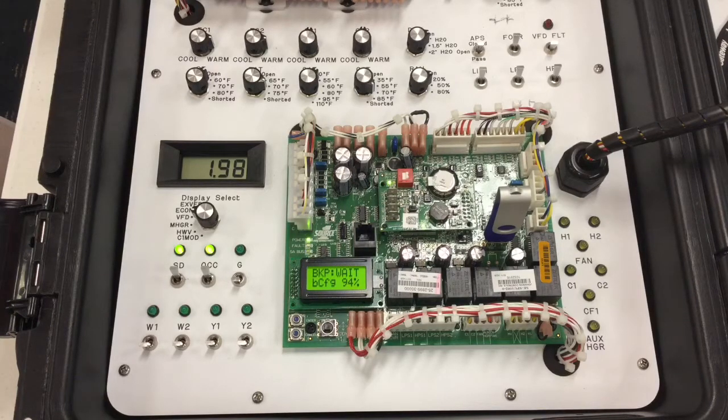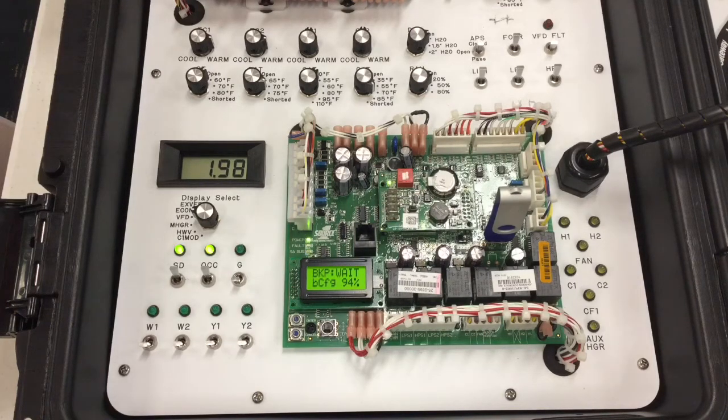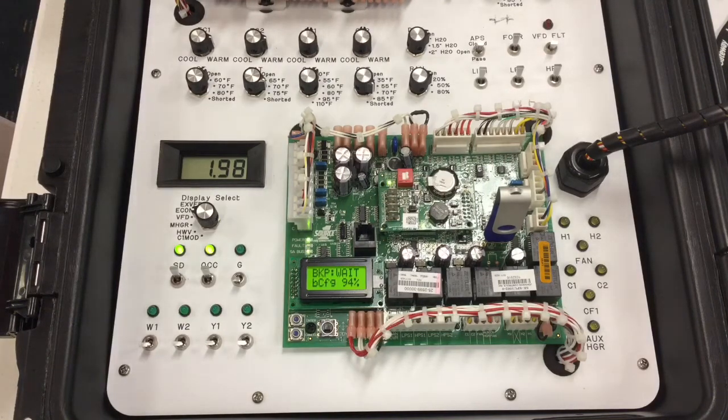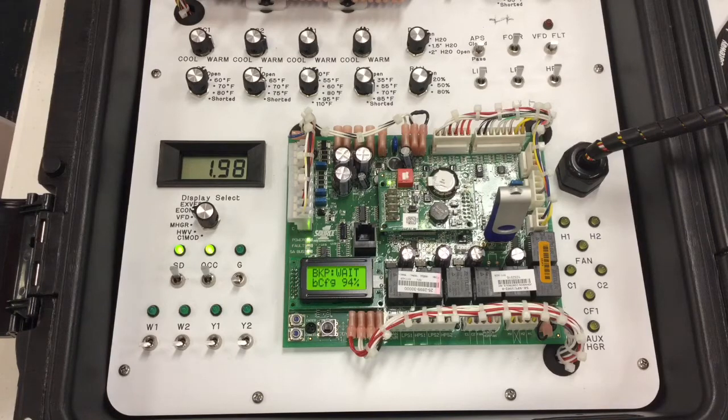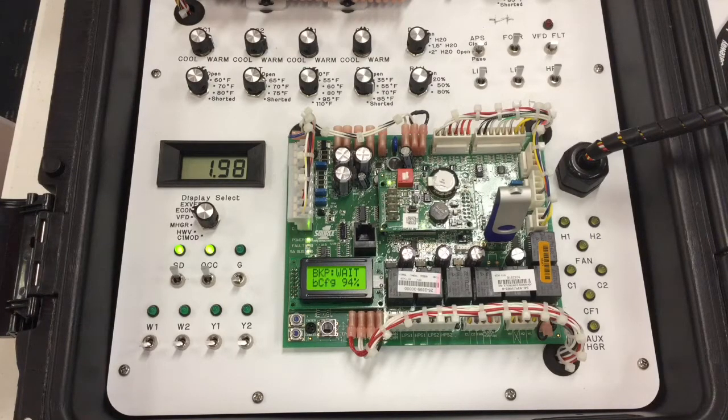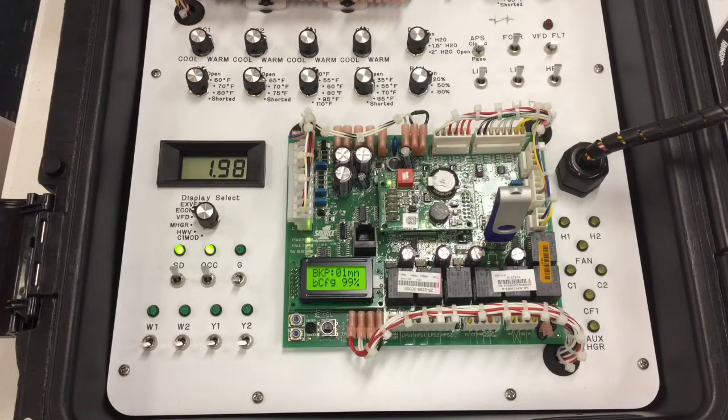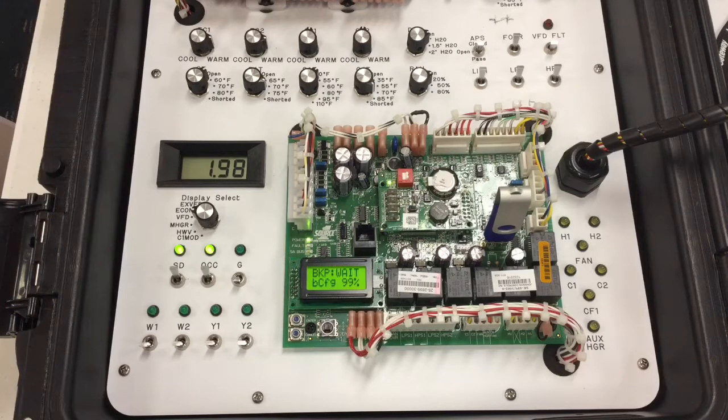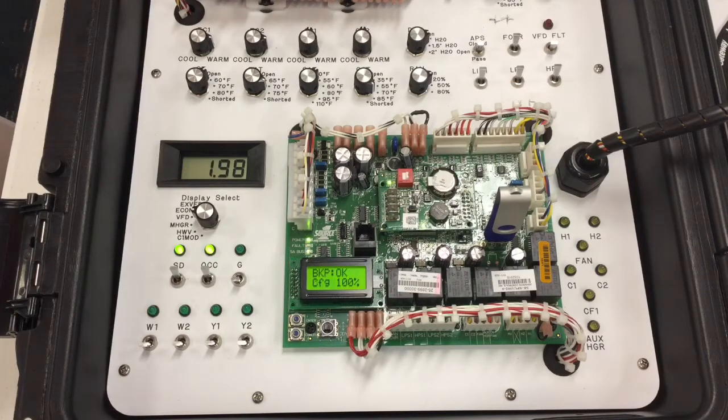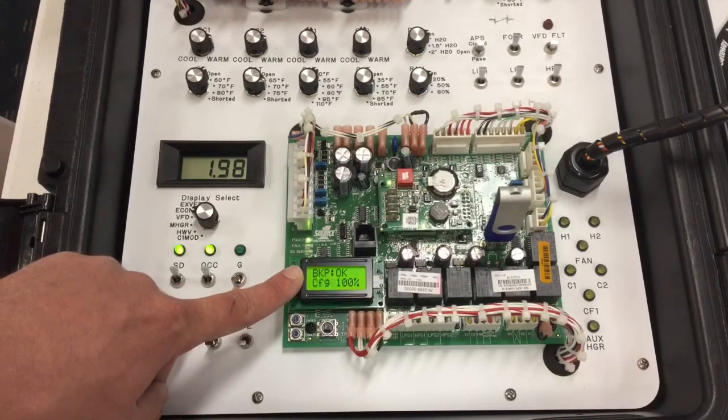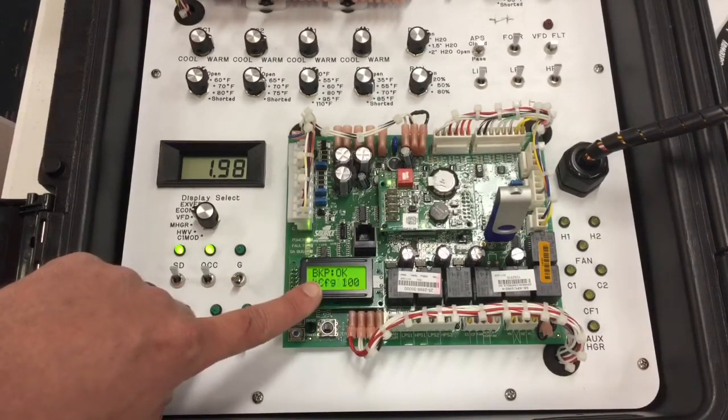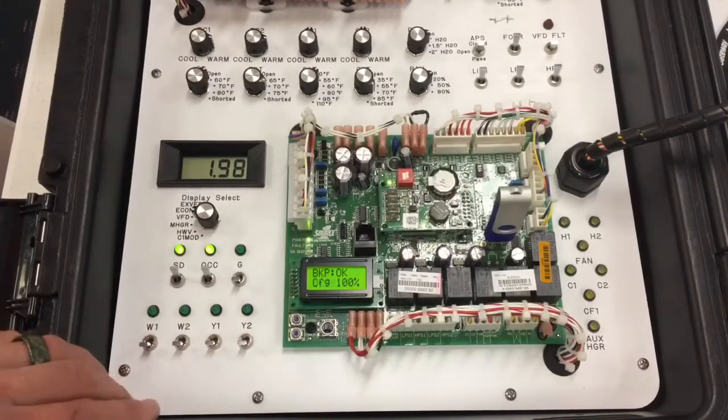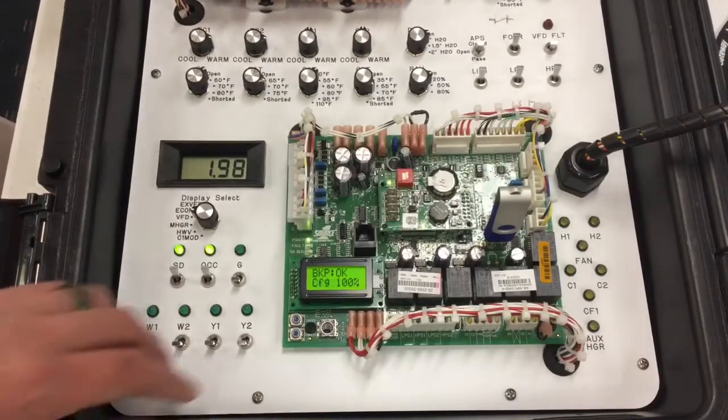At that point, you should be able to remove the flash drive, place the flash drive back into the control board and it should read USB OK scan a number. That number should be one higher than the first time you placed the flash drive into the control board. That means that the seventh file in this case has been saved successfully to the control board. At this point, you can see that it says BKP standing for backup OK. It is at 100% and it has successfully backed up.